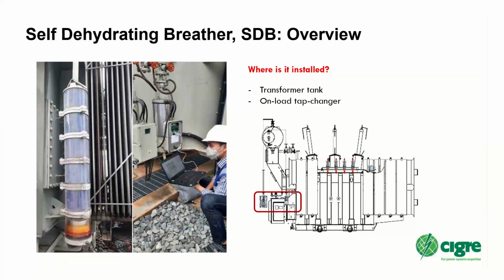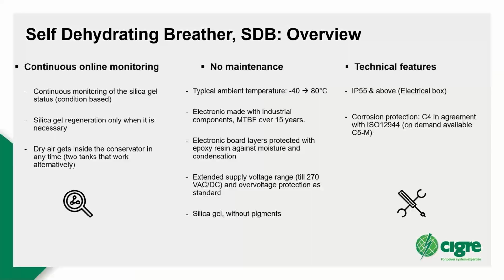So what we are trying to do is replace what you see in the left-hand figure - the old school silica gel breathers - with the new self-dehydrating breathers. These can be installed either on the main tank or on the on-load tap changer.